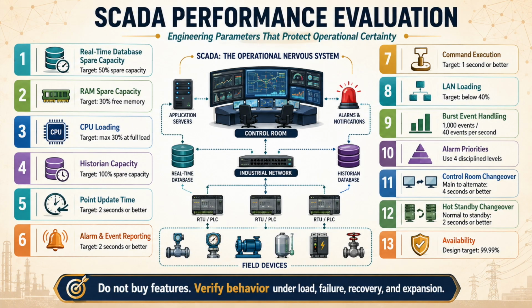A minimum 30% free operating RAM should remain available under peak tested load, and this must apply across real-time servers, historian servers, database servers, HMI clients, engineering workstations, web gateways, communication servers, and virtualization hosts, because minimum hardware recommendations only tell you what may start the software, not what will sustain stable operation during alarm bursts, historian queries, engineering access, remote sessions, backup activity, antivirus scans, reports, and redundancy synchronization.